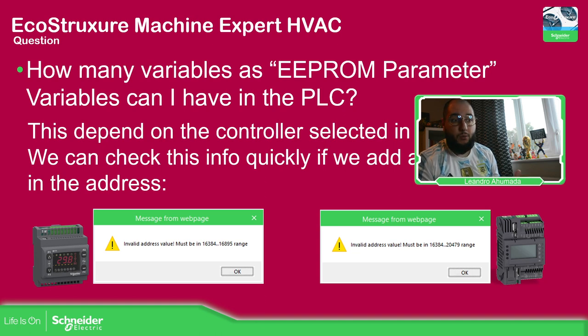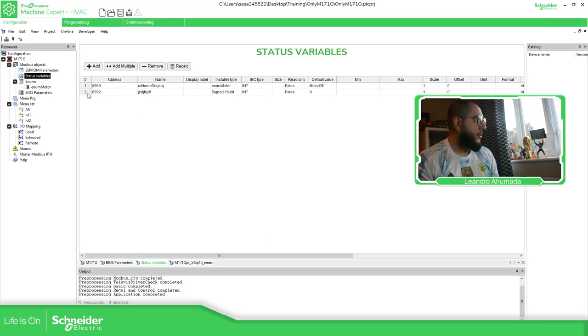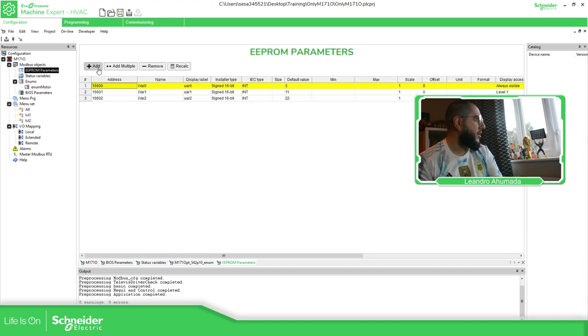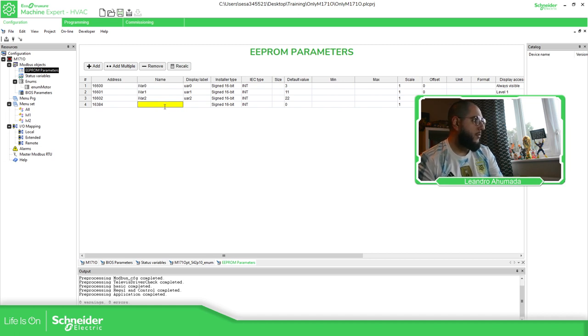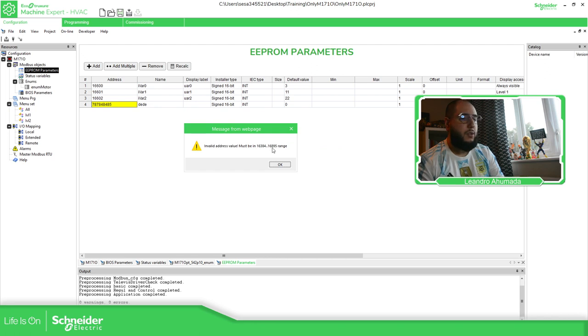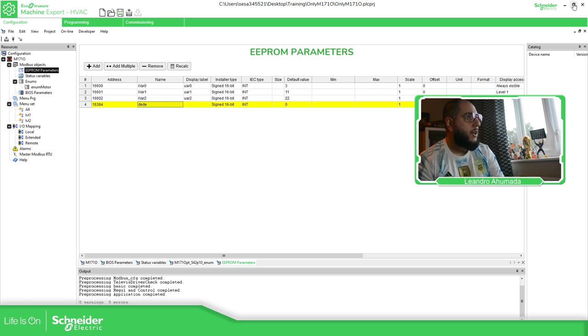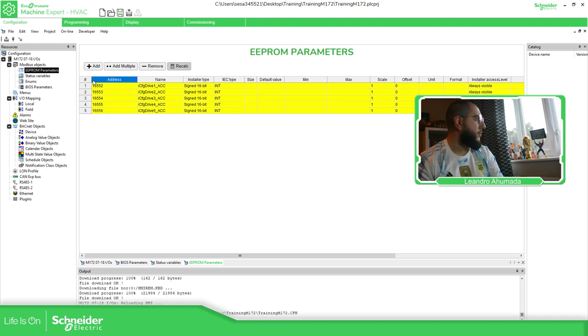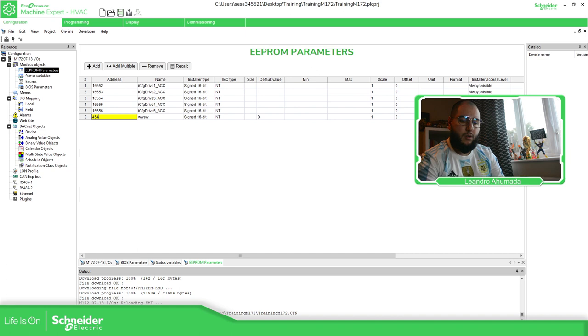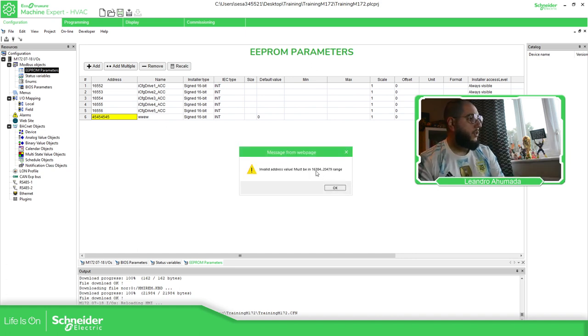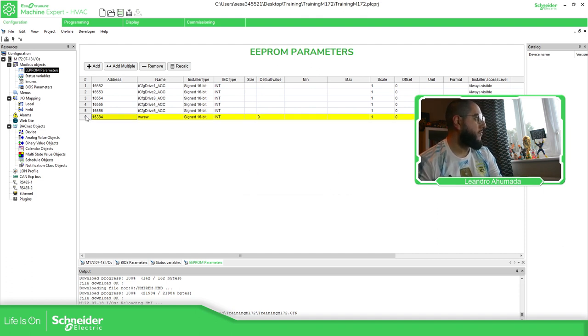To know how much memory we have or how many addresses are available, you should check the manual — but a quick way is to create a variable, select the M171, type any large number, and you'll get an error message showing you the valid range. For the M171 Optimize, the EEPROM range is 16,384 to 16,895. For the M172, the range is 16,384 to 20,479 — so there is much more space available on that controller.